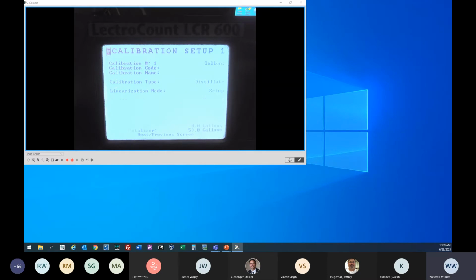So we're going to go ahead and change this to 50 gallons. And you always want to make sure that this prover quantity is what's in the prover, not what's on the display of the register, but what's actually in the prover. So we enter that, and again, you can see now our calibration factor has changed.